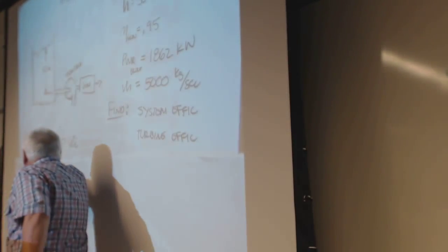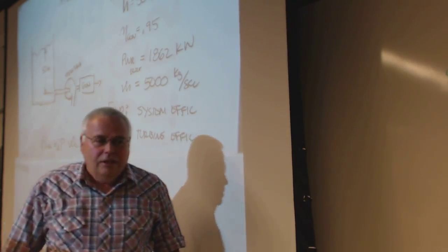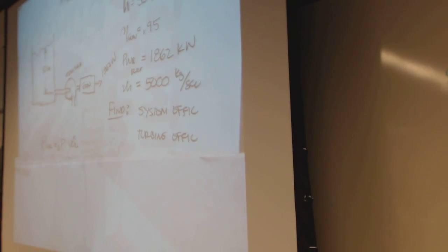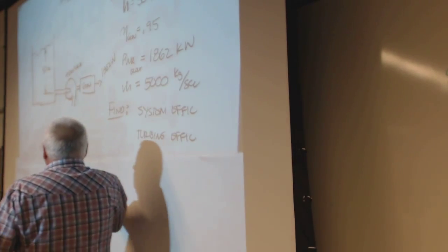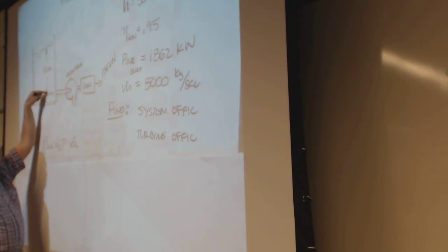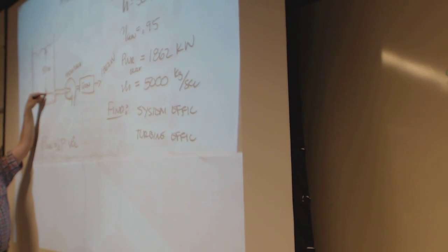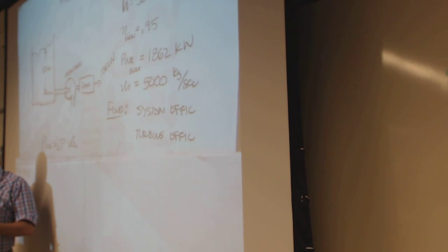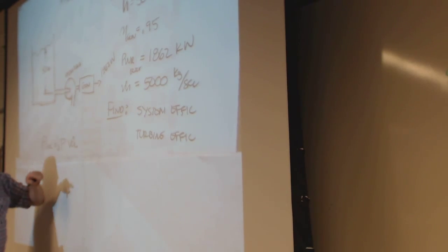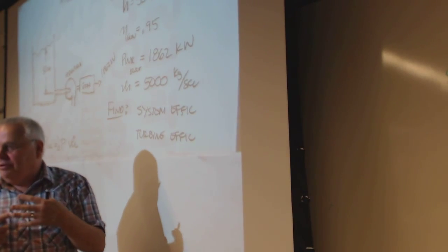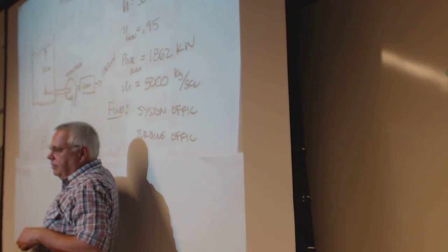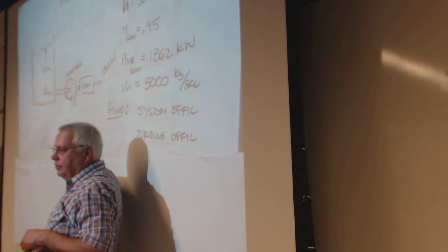So how do we get there? The power, so we know the power out. Is that a change in power that you have there? No, change in pressure. There's a low pressure here and a high pressure there, and the difference between them is 50 meters worth of water, which will give us a certain pressure. We can calculate the pressure, rho g h: density, gravity, height of the fluid. Something that's more dense will have higher pressure. We can calculate the pressure, and then we could also take the mass flow rate and assume a density at a certain temperature and come up with a number for the volume flow.